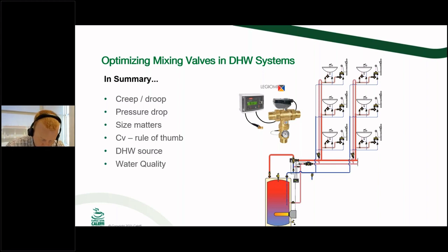And there was actually a question in some of the pre-submitted stuff about recommending additional check valves for preventing cross flow through a mixing valve. So I'm going to go off on a bit of a tangent here, but per ASSE 1017, check valves are not a requirement for 1017 mixing valves, but we do have to recommend it. Okay, so for your ASSE 1017 mixing valves, we have to recommend having check valves for potable applications or domestic hot water applications.